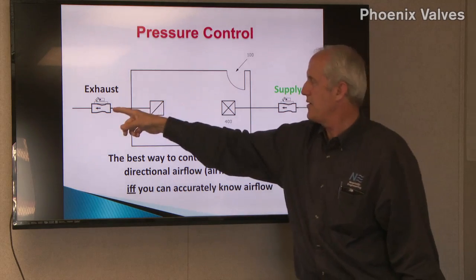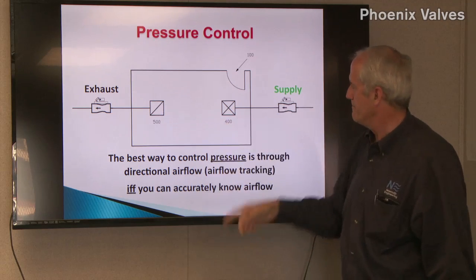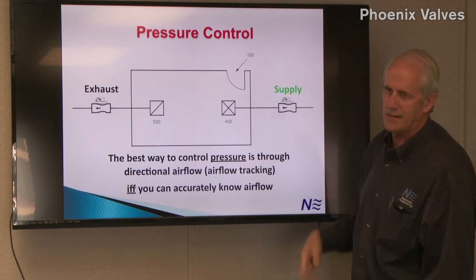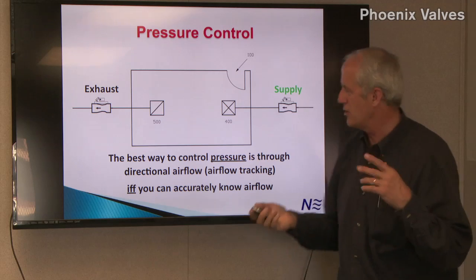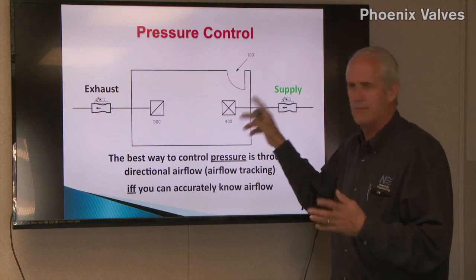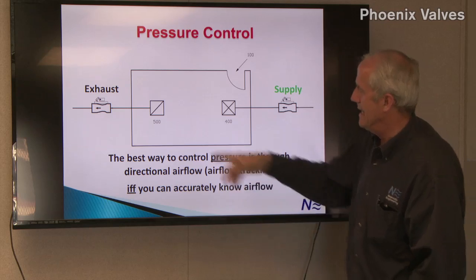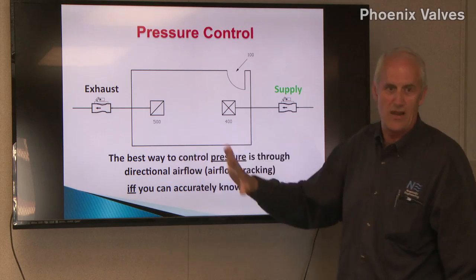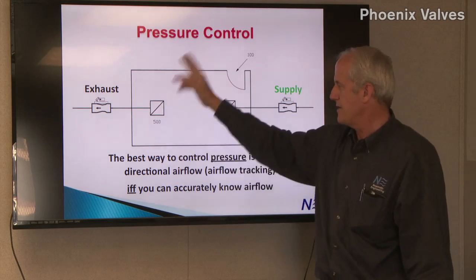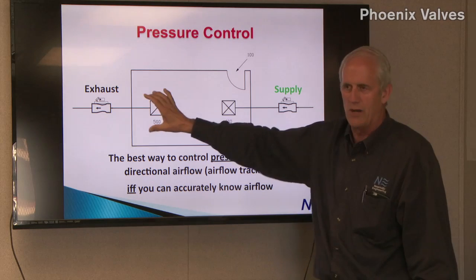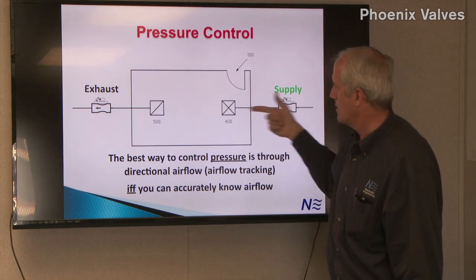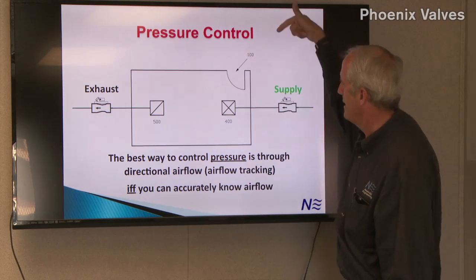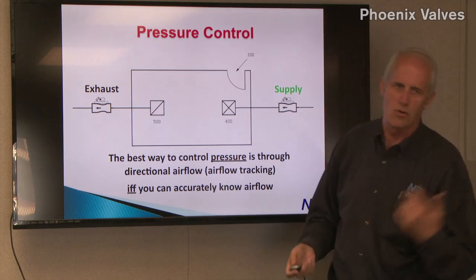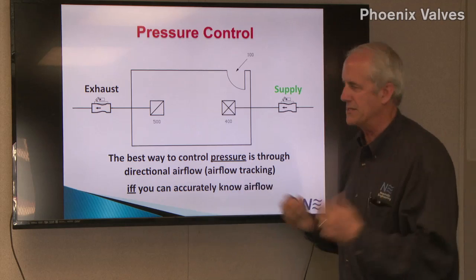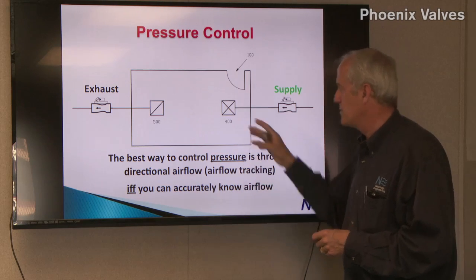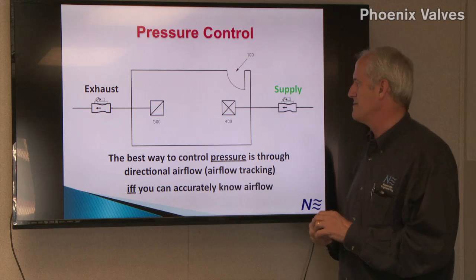Our valves are very accurate at knowing how much air is going through them. So if this guy says he's 400, he's going to be within 5% of that. He could be as low as 380 or as high as 420, but he's going to be about 400. And if this guy says 500, he's going to be within 5% also. He may be 475 or 525, but he'll be somewhere in that window. So we know that what goes in is less than what goes out, which means you're going to have air come in from the corridor to the room. And that's the basic principle behind the Phoenix system. And it's really the only way to control pressure in a vivarium properly.